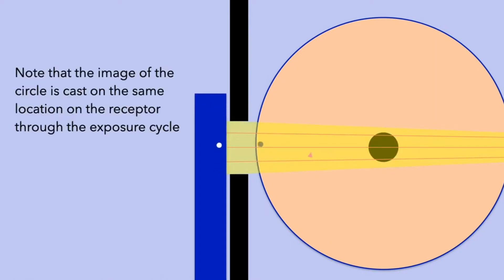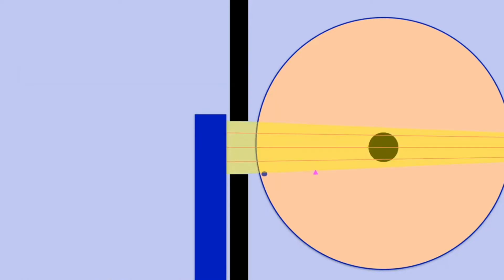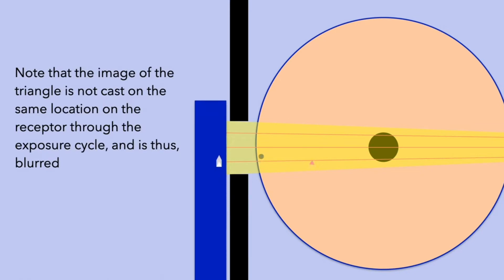Now let's take a closer look at image formation as structures move past the beam. In the presented scenario, the receptor moves past the collimator at the same speed as objects located on the outer edge of the disc. Consider an object located on the outer edge of the disc, represented here by the circle. Due to the coordinated movement of the disc and the receptor, the image of the circle is cast on the same location on the receptor through the exposure cycle. Next, consider a structure located away from the outer edge of the disc, represented here by a triangle. The image of the triangle is not cast on the same location on the receptor through the exposure cycle, and thus appears as a blurred horizontal streak.